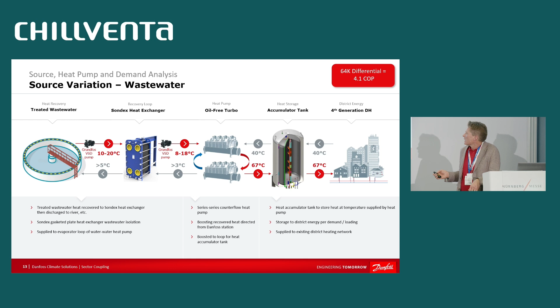So a wastewater facility is a critical facility. They have a backup power system. The only thing they're worried about is maintaining their operation, so they don't want a heat pump on site that could potentially interrupt their wastewater treatment system. So you give them a heat exchanger instead, and pipe that to a heat pump downstream of that, then build in the storage Kim was also highlighting, just in case you have a supply-demand disconnect, based also on the power available and the price of that power going into the heat pump, to then supply the district energy system.